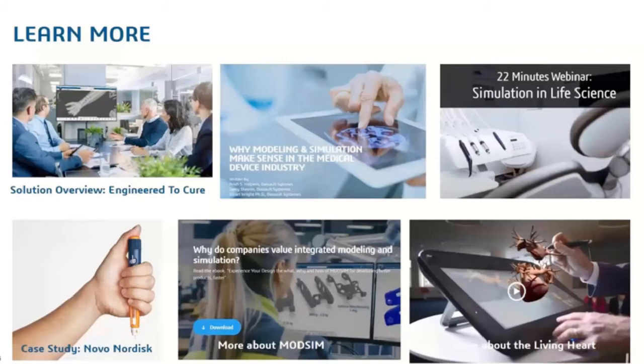But on a more secondary or implicit level, the other key advantage is that by running computational modeling and simulation, you can look at many more variations than would be possible in the real world, and you can also get much more fundamental insights into what is really happening, which you would likely not be able to get from bench tests, or certainly not from animal or human tests, where you might get a result that something works or fails to your satisfaction or does not meet your performance indicator, but it's unlikely that you'll be able to pinpoint exactly why. So by gaining those much deeper insights into how your device might be performing, you could arrive at better designs, less testing in the future, and in an overall sense, work towards decreasing the overall development time and cost by adopting modeling and simulation, both from the direct and the indirect approaches.